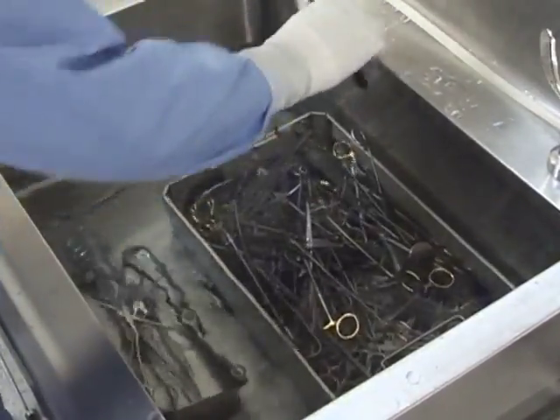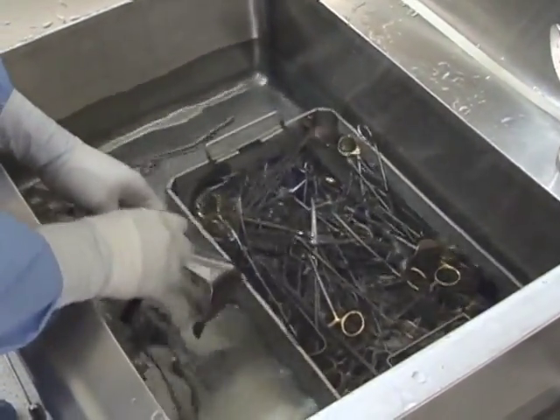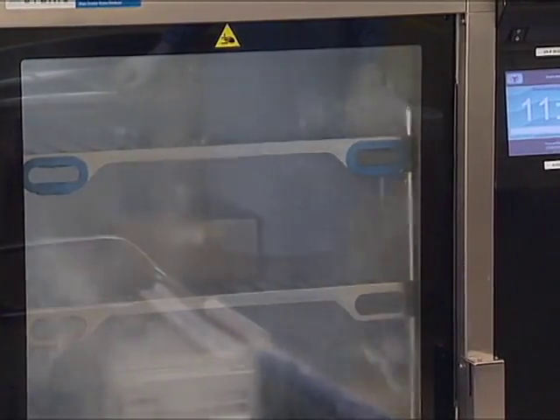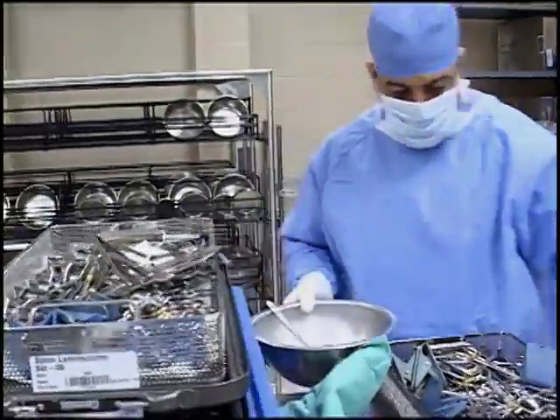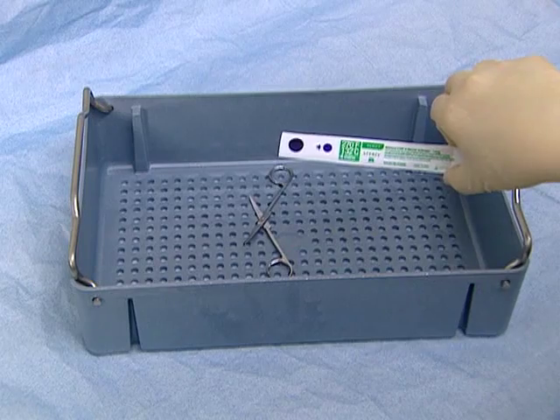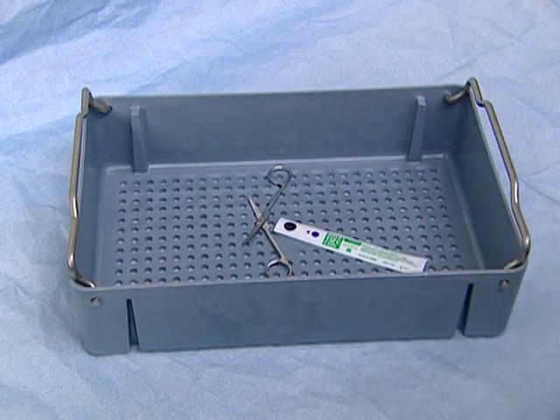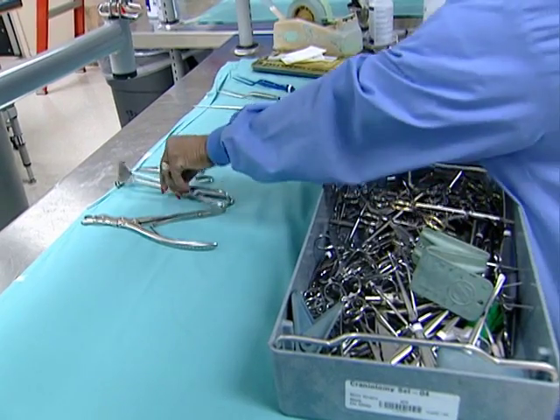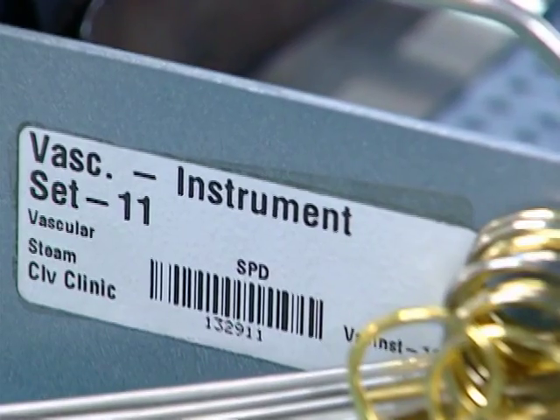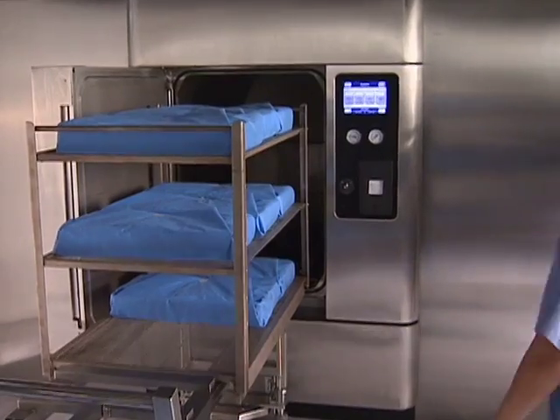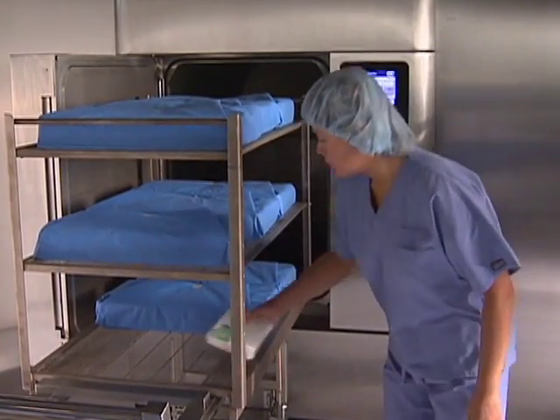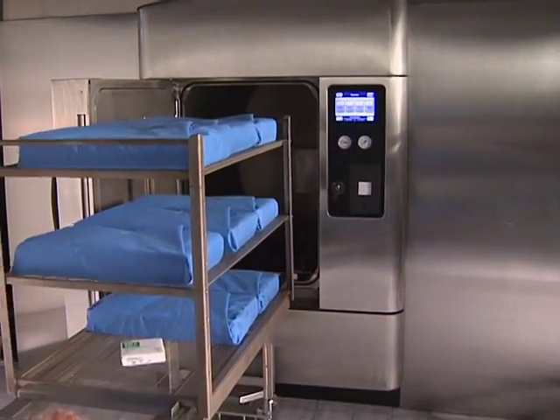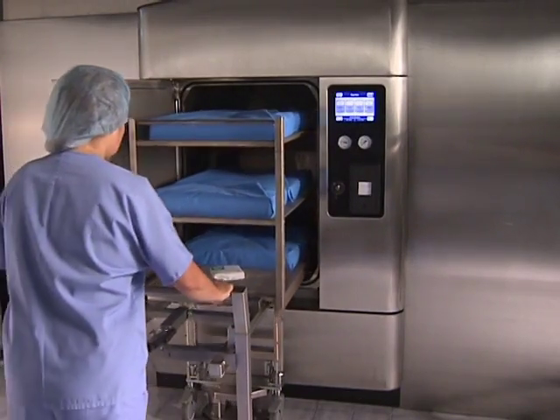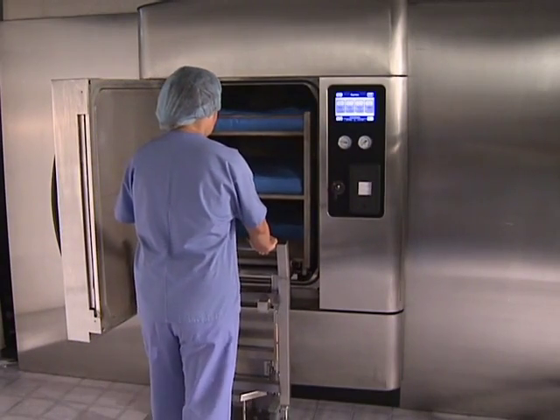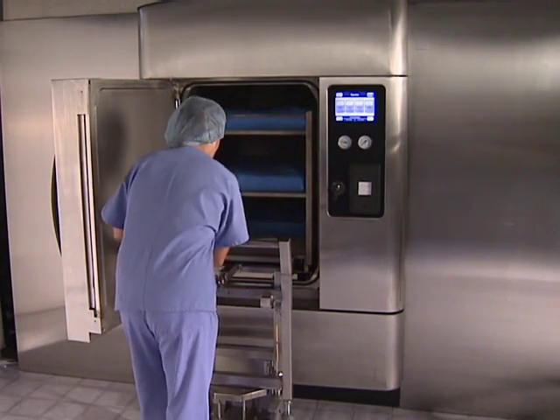The sterilization process includes these general steps: manually or mechanically clean instruments to remove visible soils, dry instruments thoroughly, organize instrument trays, include pack control sterility assurance monitoring chemical indicator, package instruments and instrument sets, label and document packages, include load control sterility assurance monitoring indicator, properly load the sterilizer. Be sure to understand and follow your department's policies and procedures regarding the processes involved with these steps.